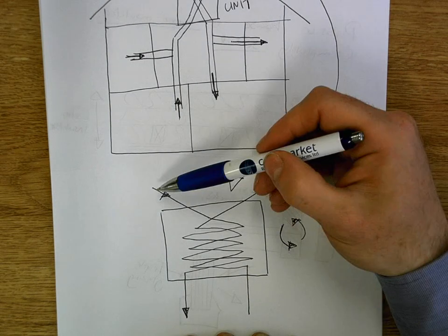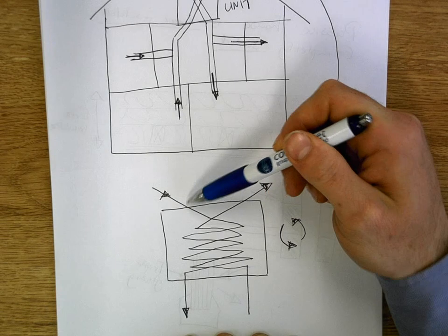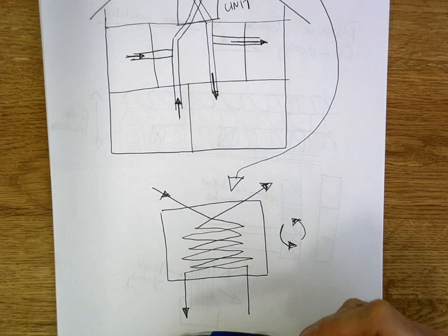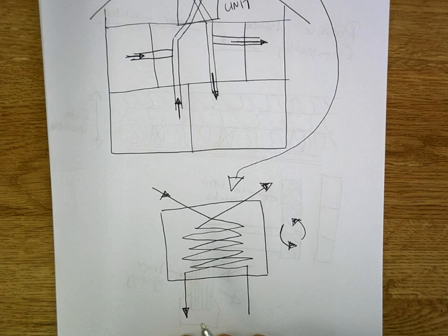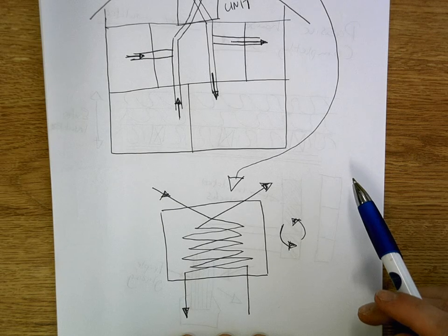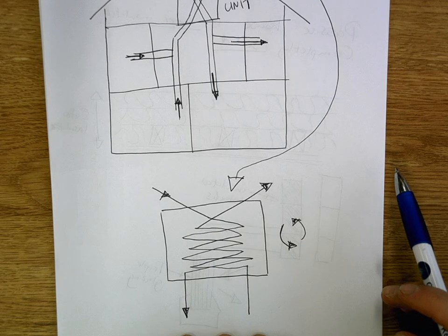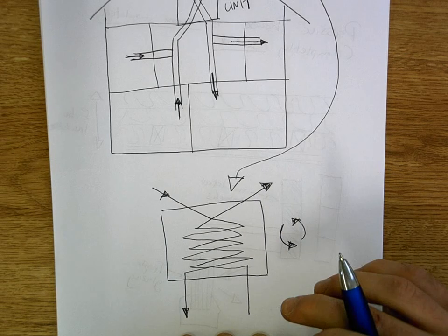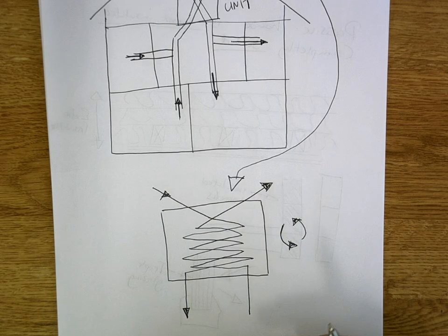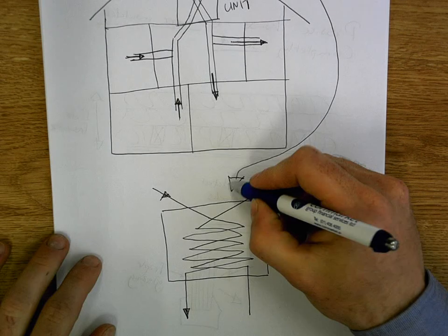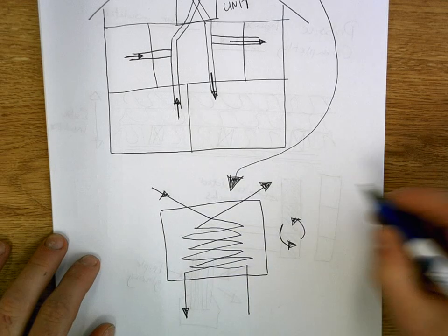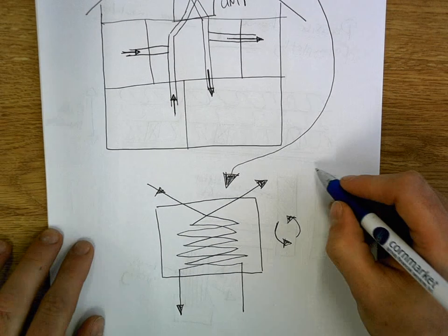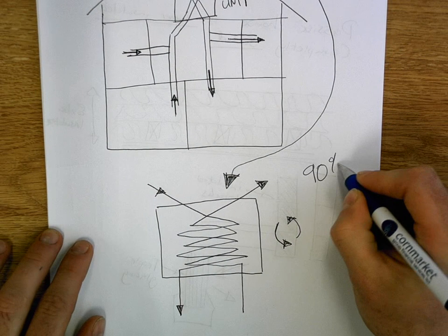So when you have fresh air coming in that's outside temperature, by the time it actually leaves the unit, it's increased in temperature by a huge amount through that transfer of heat. So you have to be clear on that in your answer. The air itself doesn't mix, it's just the actual heat or the energy from one pipe to the next that is transferred. Now usually they will say, what they claim anyway, is that your heat retention can be up to 90%.